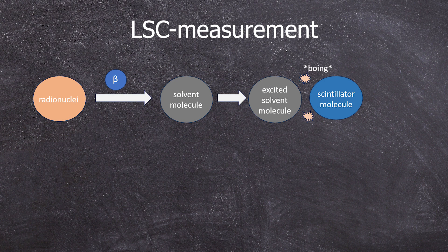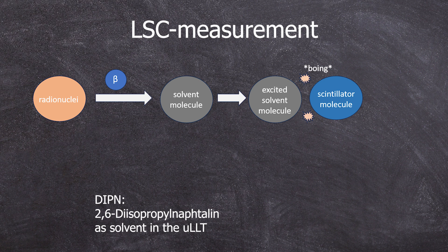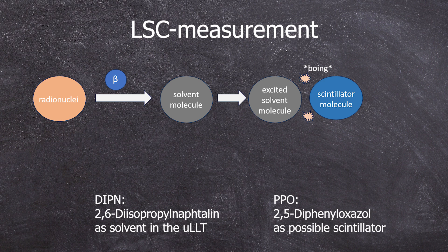Now I can directly answer why tray delay is so important. A measurement in the LSC only works if a particle decays, excites a solvent molecule, and this excited solvent molecule then collides with a scintillator molecule, transferring its energy to it. The scintillator then emits this excess energy in the form of light, which can be measured as a signal.